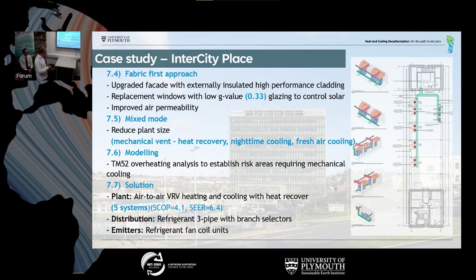The next thing we did was try to complement the university's strategy to reduce cooling. One way was to use a mechanical ventilation system that could make use of outside air to cool the building. That provides an opportunity for nighttime cooling too, which is typically colder overnight. We also had heat recovery, so we could recover the heat from the room air, reducing both the heat load and cooling loads on the building. As I said, modeling helped with that.